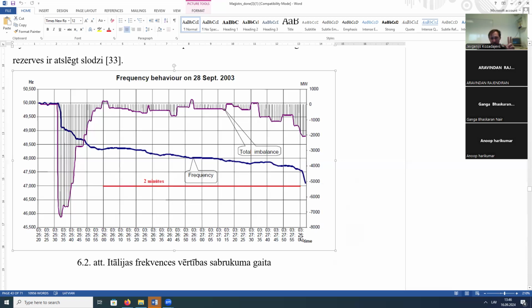It means that during 2 minutes, under frequency automation used all the possible stages and disconnected all the possible loads, but because we lost more generation every second, frequency dropped to a critical value, then everything disconnected and it was a blackout, no electricity in Italy at all. The power system stopped existing as a united system. So it was a blackout.